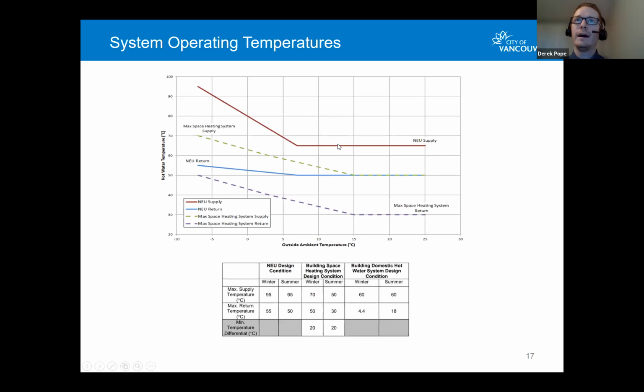When it's warm, we can meet our system demands with a temperature of 65 degrees Celsius, which really allows us to leverage our heat pump technology. As it gets colder out, we need to increase the supply system temperature to meet the system demand, and that's when we start supplementing a bit with our gas boilers. Our heat pumps can do up to 80 degrees Celsius, and beyond that we really need to make use of the gas boilers, to meet the building's requirements. On the coldest day of the year, a building is typically designed to need about 70 degrees Celsius.